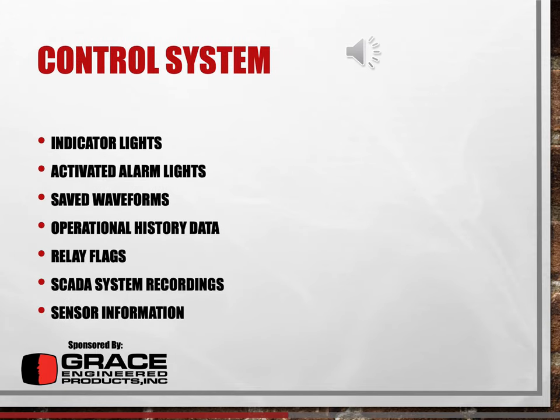Next, you'd want to go a little bit more into the control system, and not just the relays, but more of the actual SCADA system and the PLC overall system, the hierarchy. So these are the kind of things you want to look at. We've already talked about them, so I just wanted to put them again on the slide. We're talking about indicator lights, activated alarm lights, saved waveform captures, operational history, relay flags, SCADA system recordings, and even sensor information.